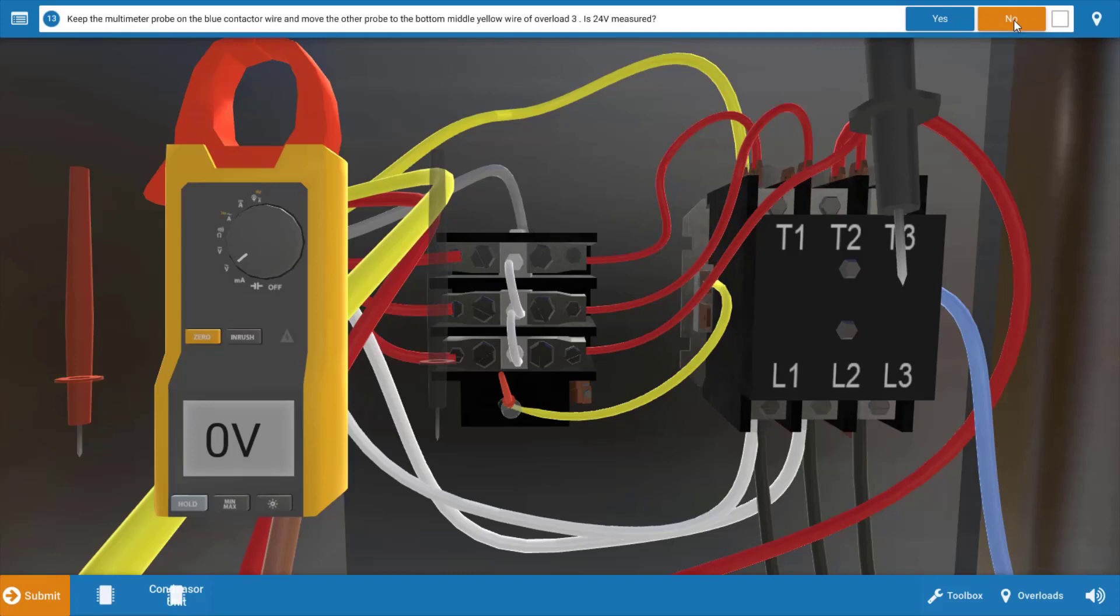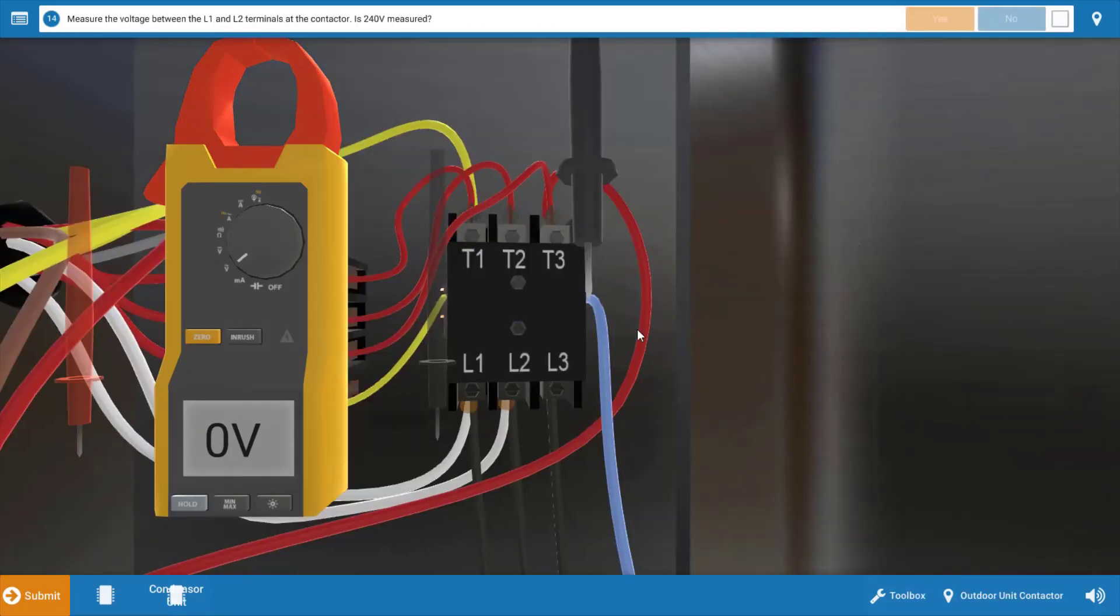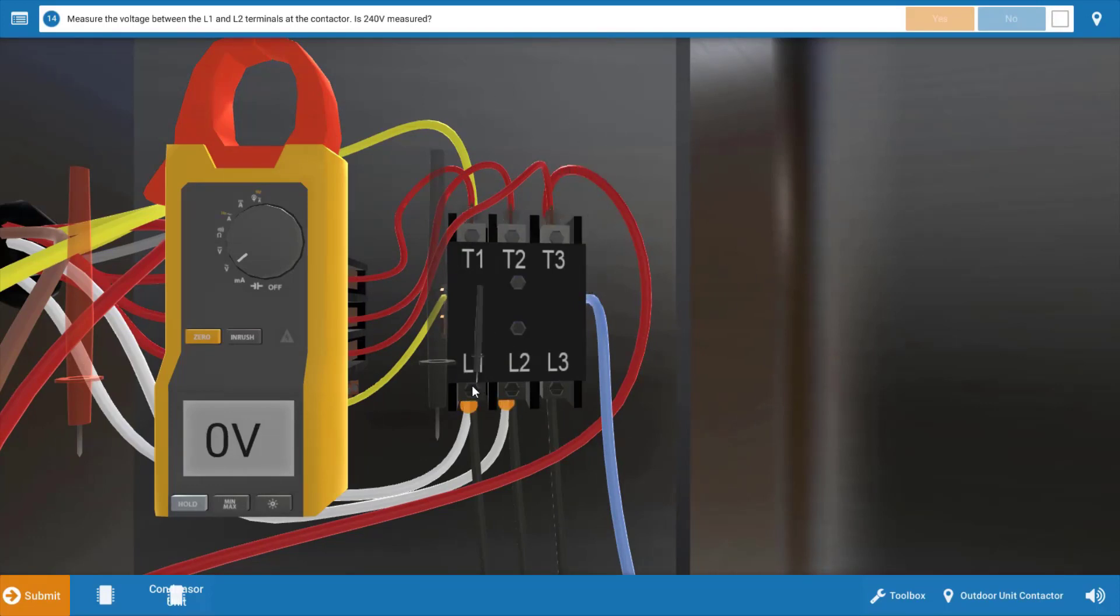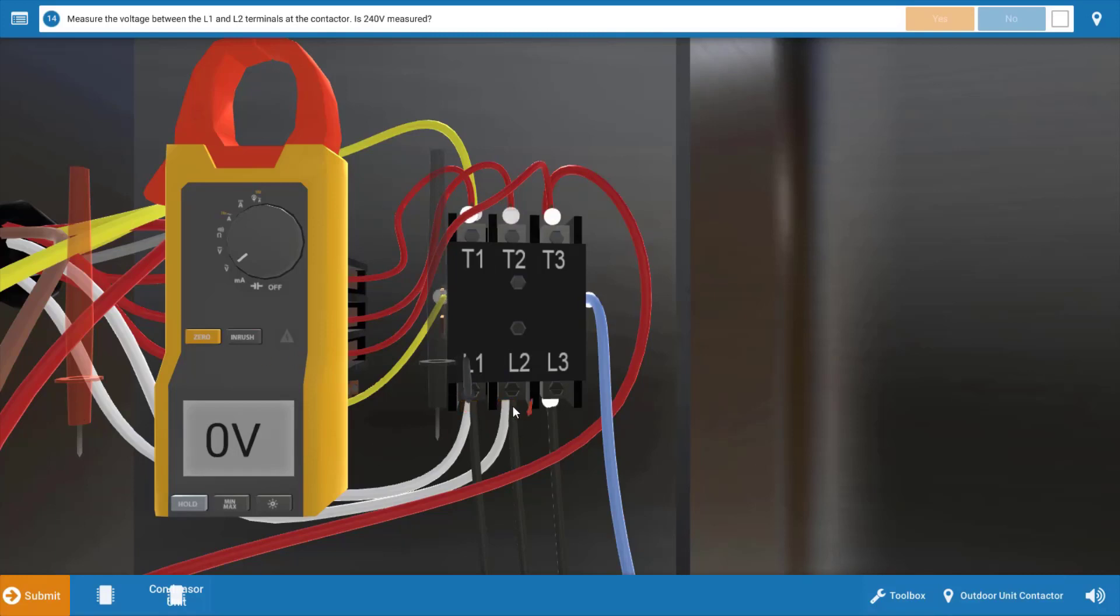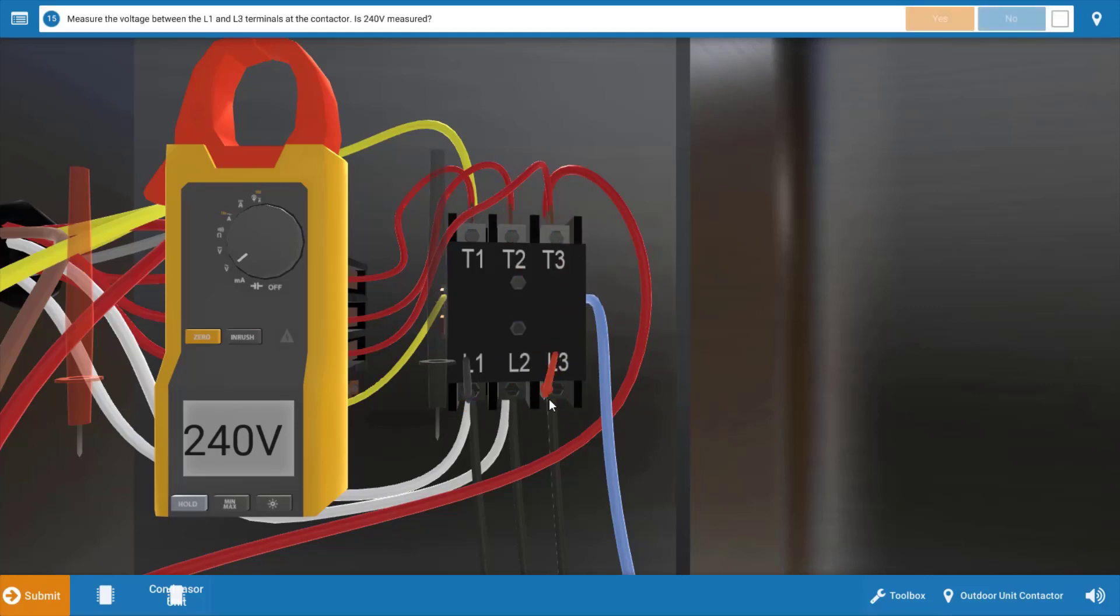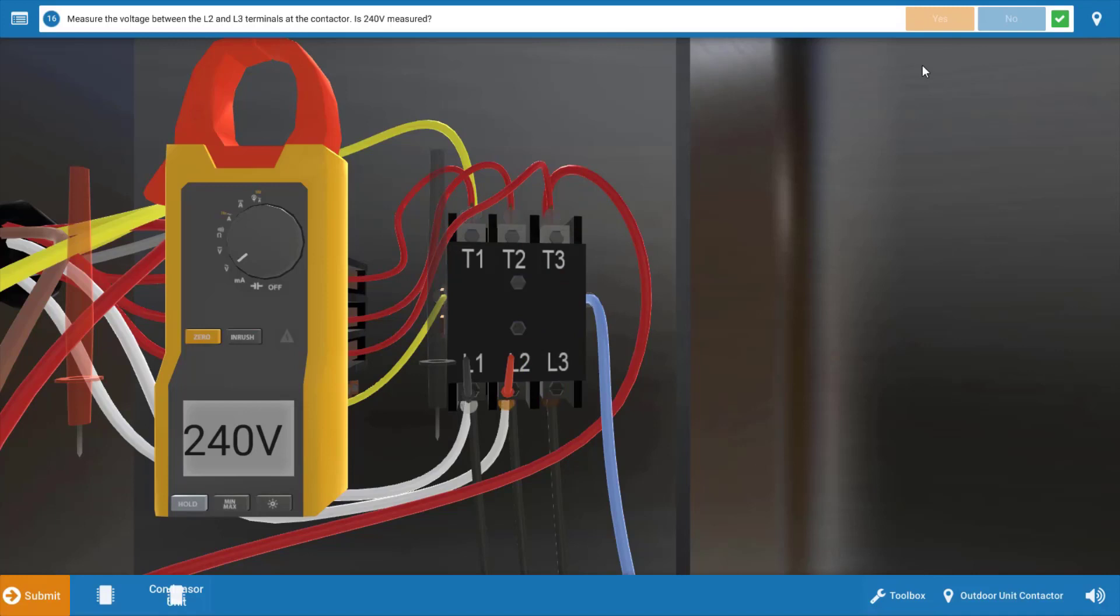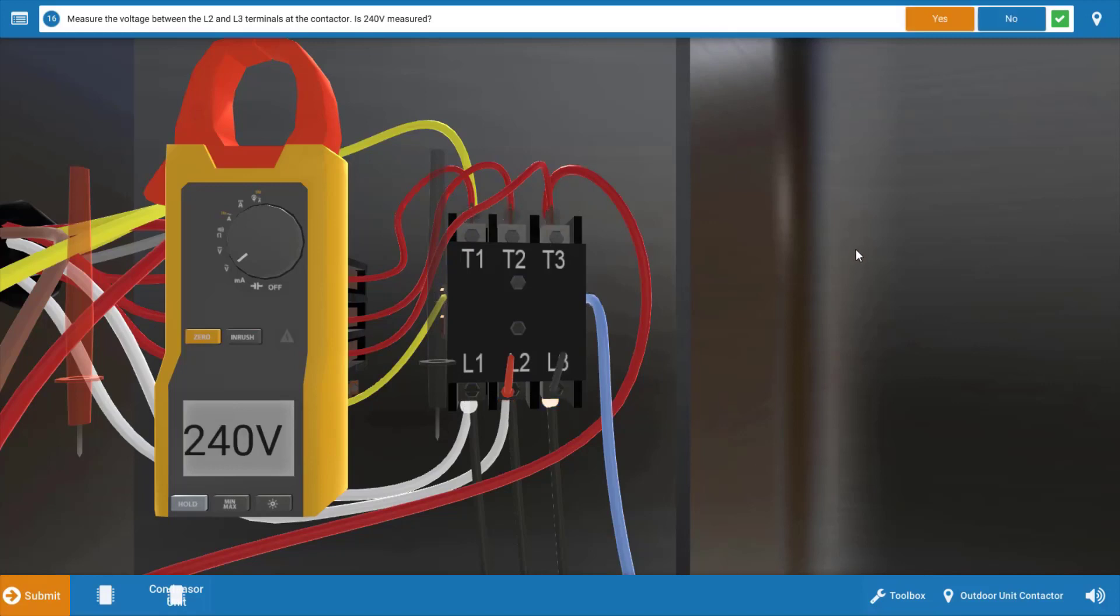So now that we click no that we didn't measure 24 volts, we measured zero, our next step is to measure for power coming into the contactor at each phase. We're going to go L1 to L2 first, and when we do that we've got 240 volts, so we can click yes. Next we're going to go to L1 and L3 and we have 240 there, so we click yes. And last but not least, L2 to L3, and we have 240 there. So pretty much at this point we have power coming into the contactor, meaning it's not a blown fuse.